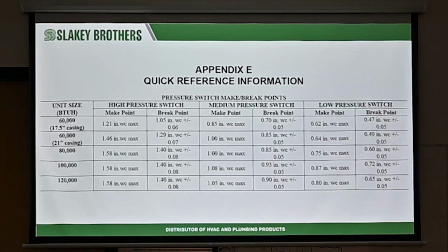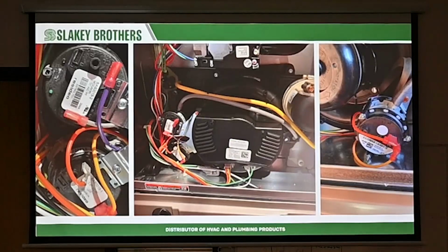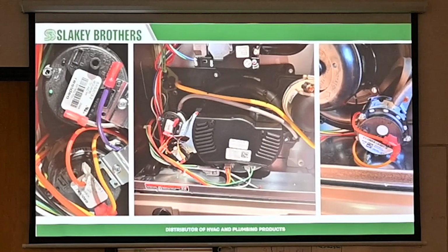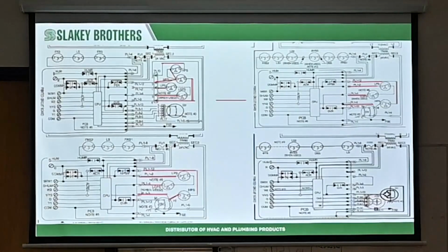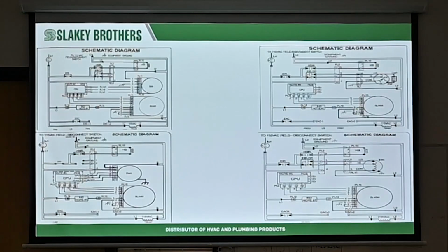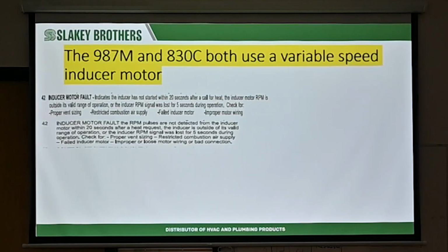If that switch does not close 0.15 to 0.2 above it, and your pressure is above those numbers and the switch is open, then that switch is faulty and needs to be replaced. And just some live pictures I took of the equipment showing those pressure switches. These are just on the blower motors.